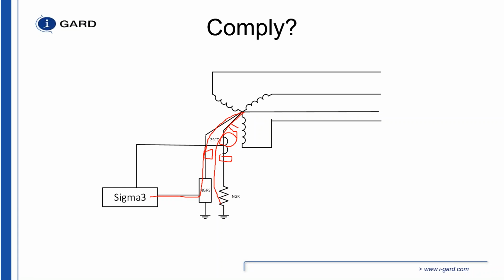Short is actually easy to do, but the open part is very difficult. And this comes from use of electricity in mines, which we've been doing for a long, long time. Part of the problem is that we have to monitor the integrity of that resistor when the power is off the system. When the transformer is de-energized, we still have to actively monitor the integrity of that path to ensure that the resistor is in the circuit before we're allowed to actually turn on the power.